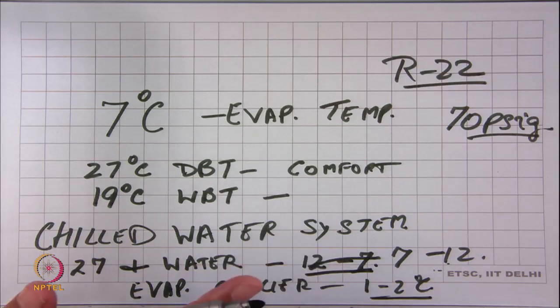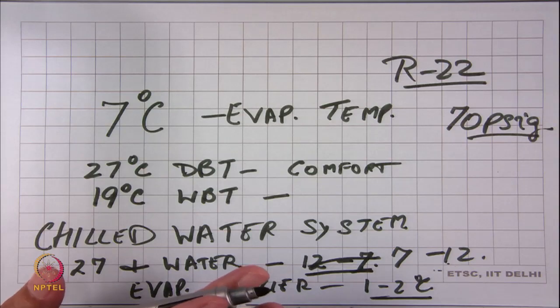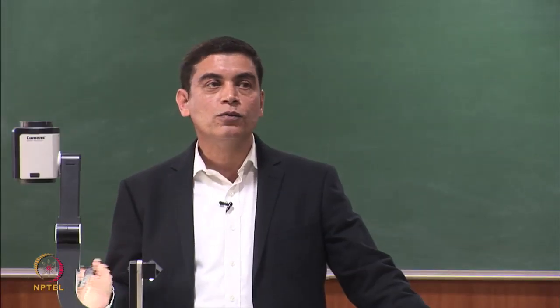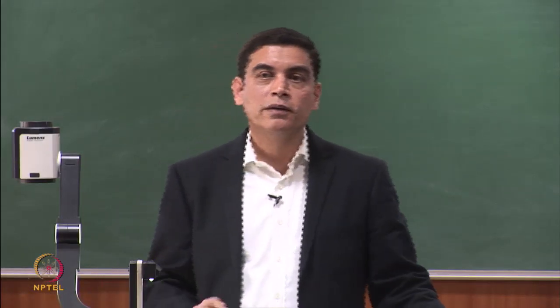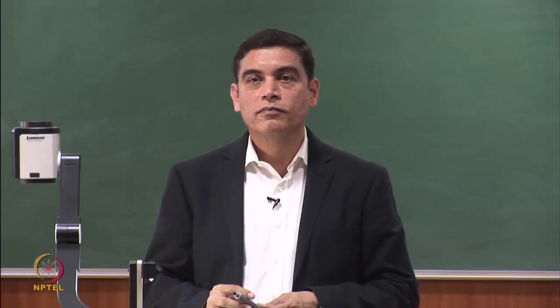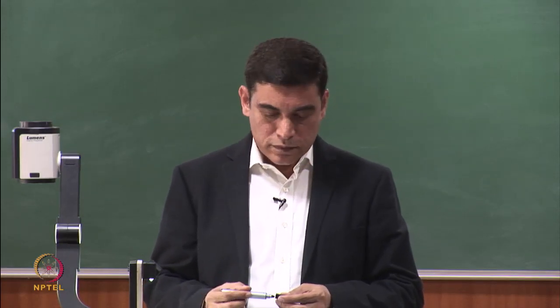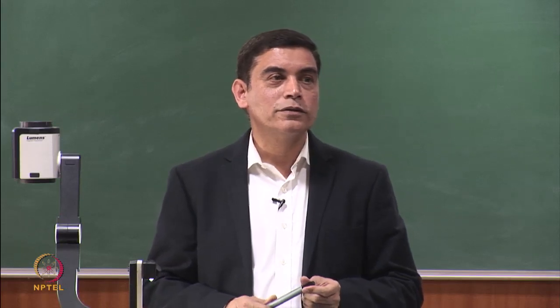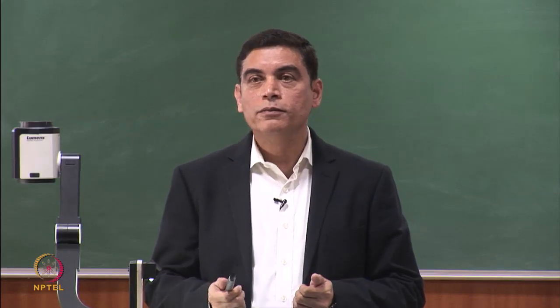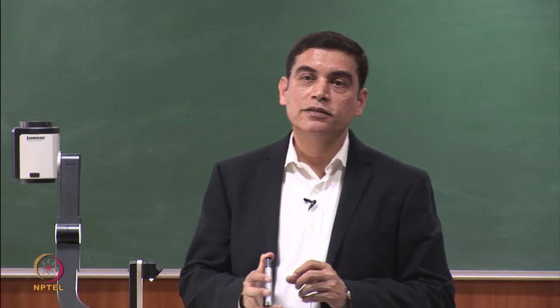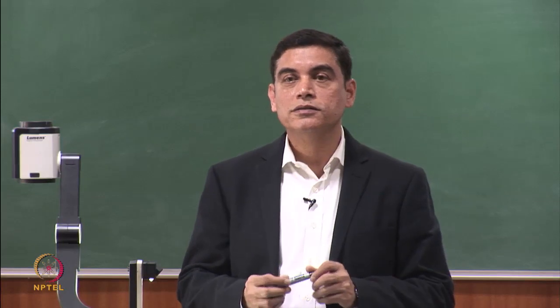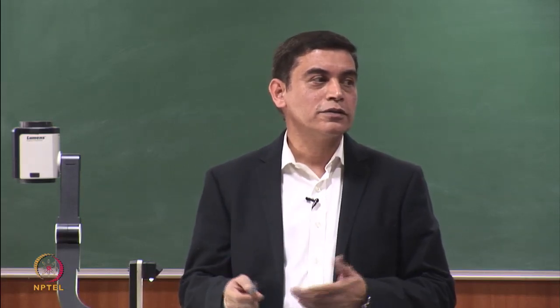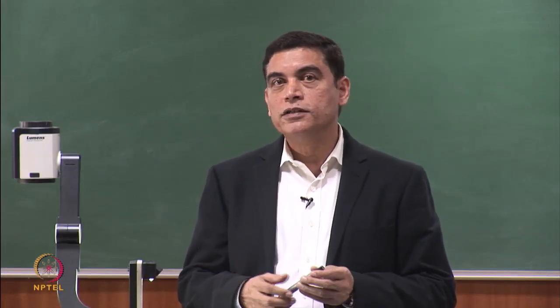The convenience that drives chiller use is when we have large applications with multiple indoor units. The newer systems overcome this difference — instead of having several indoor units transfer heat to water and then water in another heat exchanger to refrigerant, they use multiple indoor units directly transferring heat to the refrigerant. So the 5-degree difference is not there. If you look at a compressor performance curve, the power consumption is most sensitive to the suction pressure and therefore the saturation temperature corresponding to that, which drives the development of newer systems.